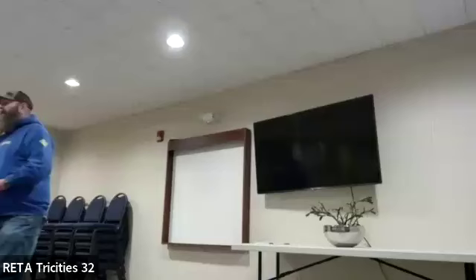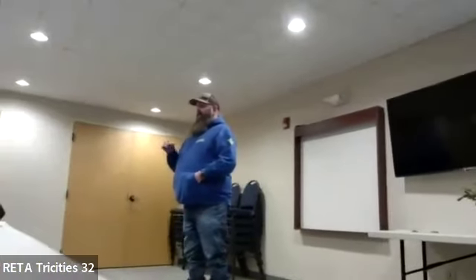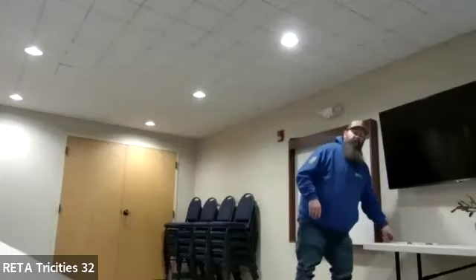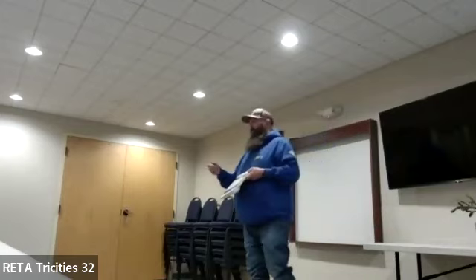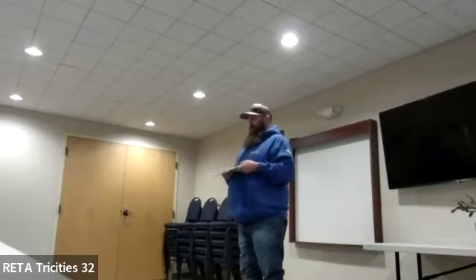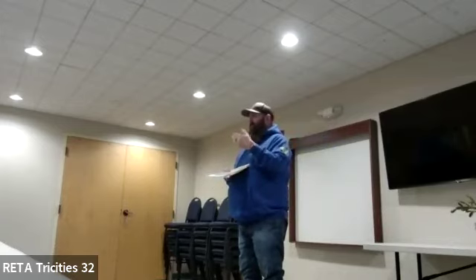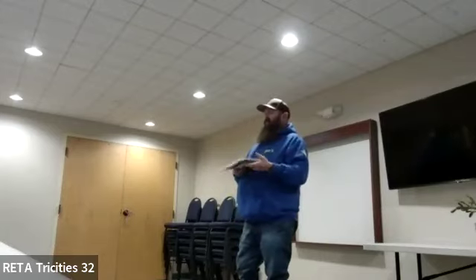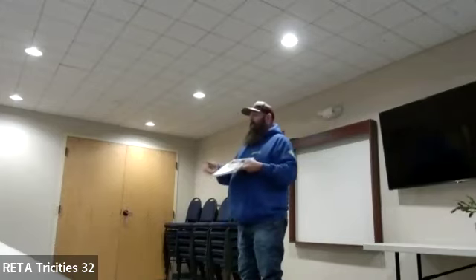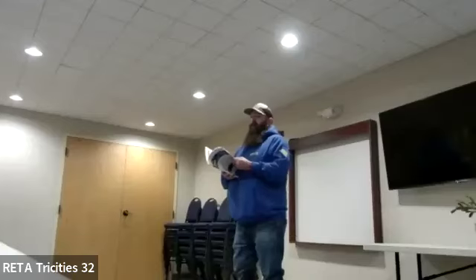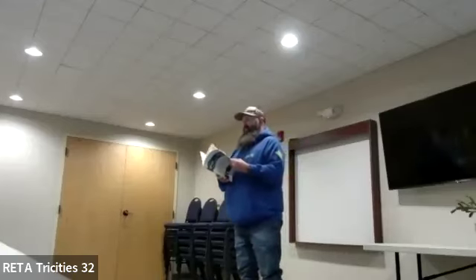I put a general duty in there and a compressor, just so everybody can compare. They dull down some of the substance info in the top box that we used to all love filling out. If you already had them filled out, it's just our annual inspection for checking the boxes. The new ones have a lot more boxes to check and they get a little more thorough for your inspections on each piece of equipment. They still have some of the pertinent information that's good for your filing systems, for motors. You know, not so much on the extra technical jargon. If you look at the comparisons, you can see they build it down to the important things. I mean, the three-phase, frame, horsepower, all that extra minutia of having your serial number for your motor. I don't know why you think you would need a serial number for a motor, since most of your vendors won't get you a motor right away with that. They're gonna want to know horsepower, frame, and RPMs to get you a motor.